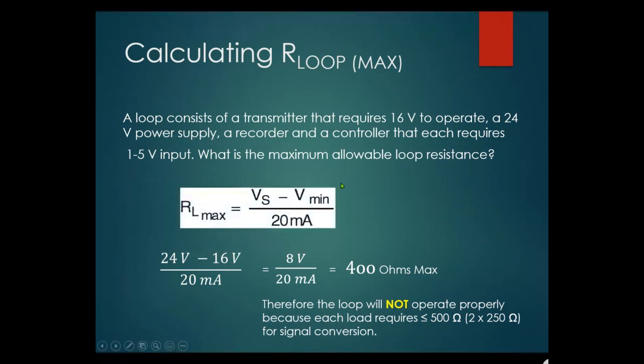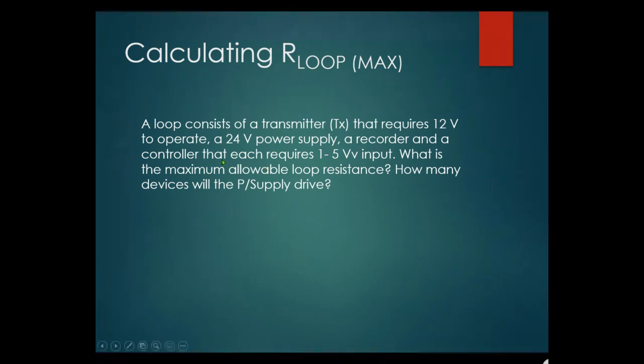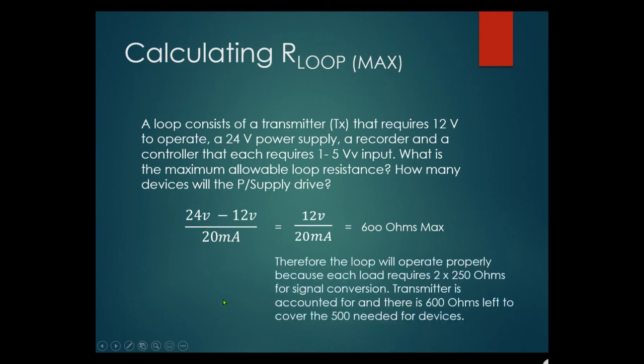Second example: a loop has a transmitter requiring 12 volts to operate, a 24 volt power supply, a recorder and a controller each requiring a voltage input across 250 ohm resistors. Maximum loop resistance: (24V − 12V) ÷ 0.020A = 600 ohms. Therefore the loop will operate properly since each load requires 250 ohms — two loads equals 500 ohms, which is below the 600 ohm maximum.